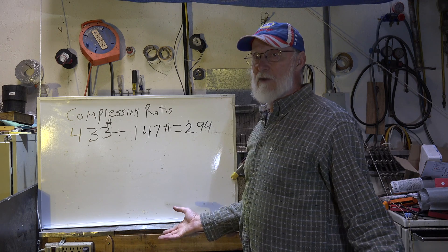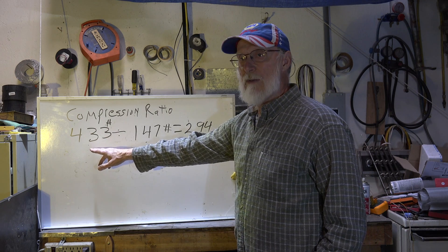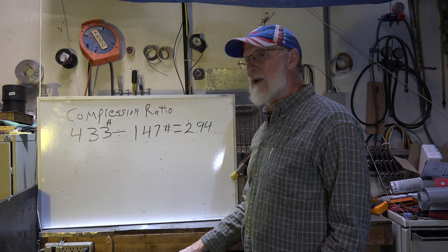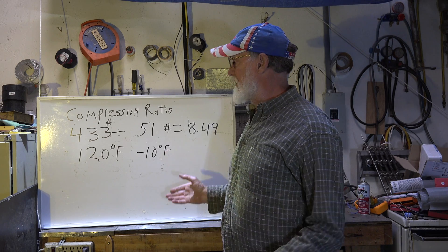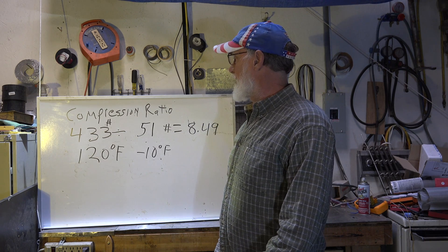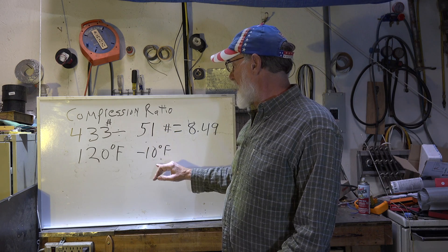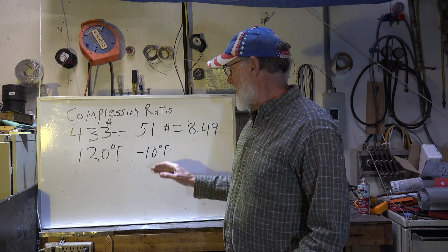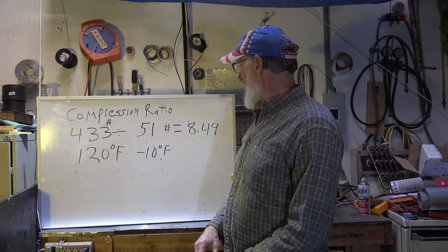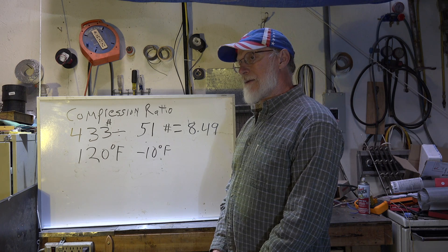Essentially 3 — a compression ratio of about 3. Now let's change the suction pressure and see what happens. I'm not going to change the condensing side because that corresponds to outside temperature. I still have 433 on the discharge side, but now I've put the suction pressure down to 51, which corresponds to minus 10 degrees — that's going to give me a box temperature of maybe around zero. When you calculate it out, it's 8.49, essentially a compression ratio of 8.5.